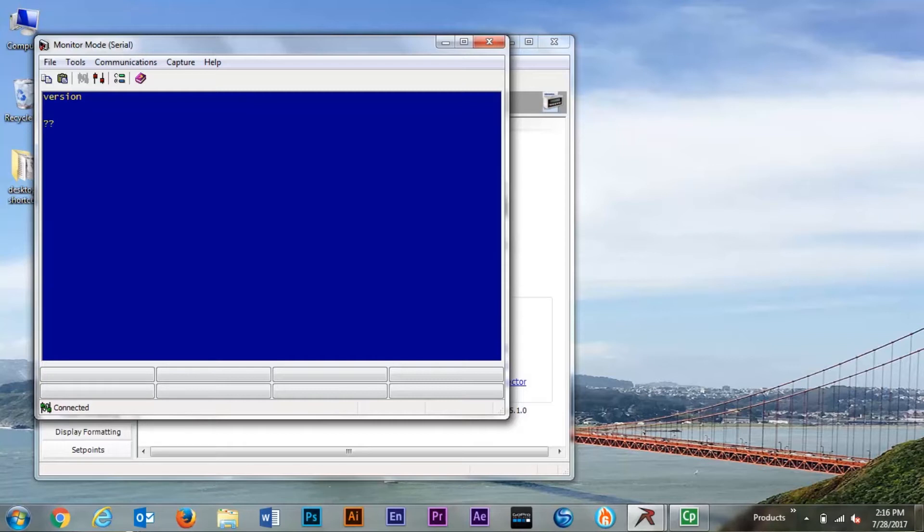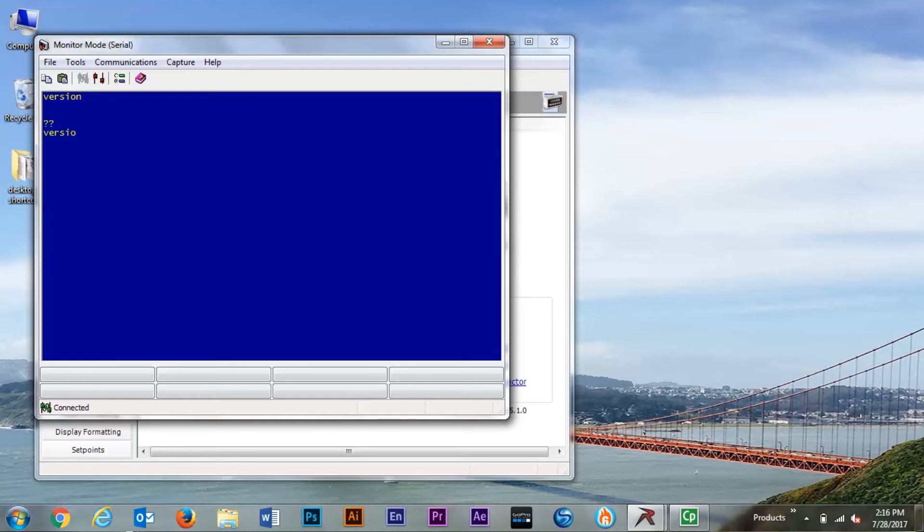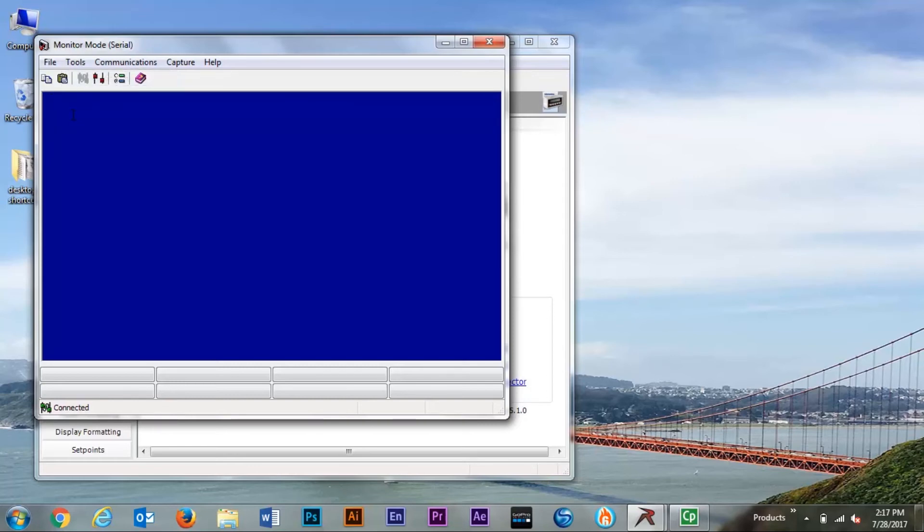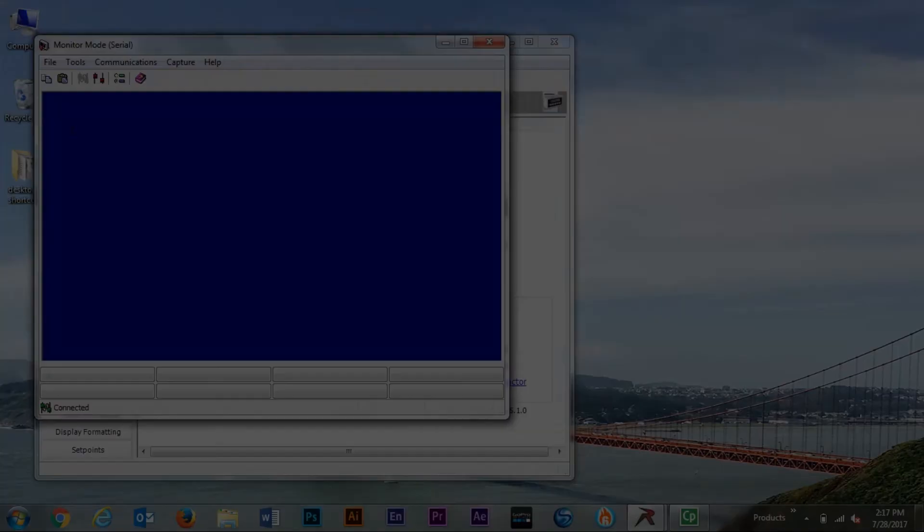As we hit enter, you do see two question marks appear on the screen. That means we have communication, but it didn't understand the command. At this point we will type in version. And as you can see, we get a response from the indicator, Version 3.0 of the 880 indicator. This has been a demonstration of how to troubleshoot RS-232 on the 880 indicator.